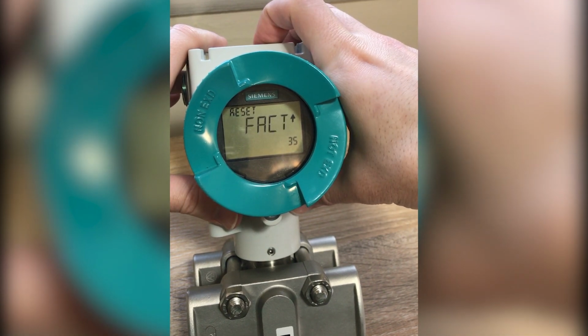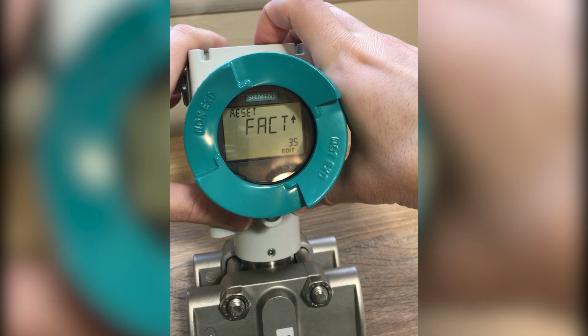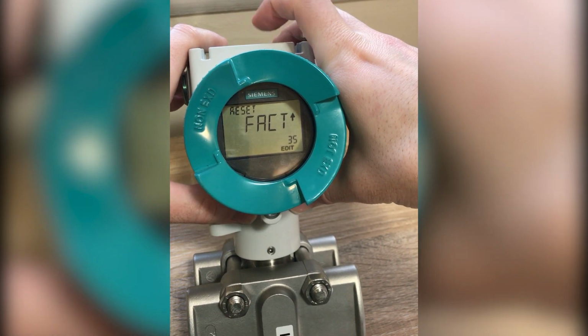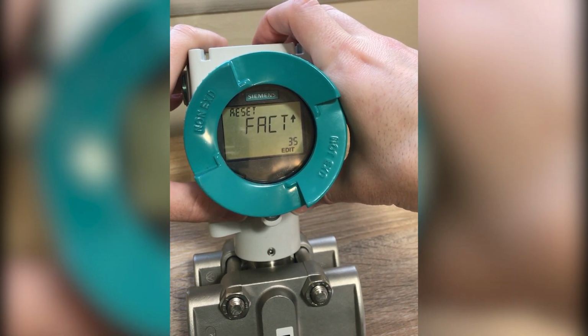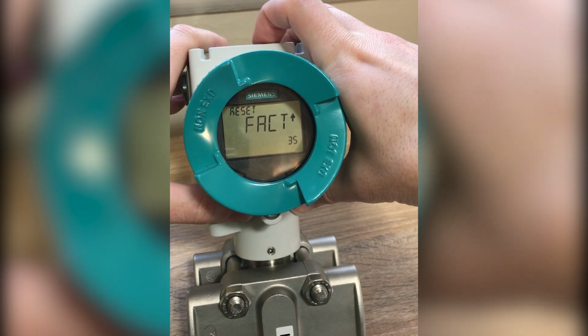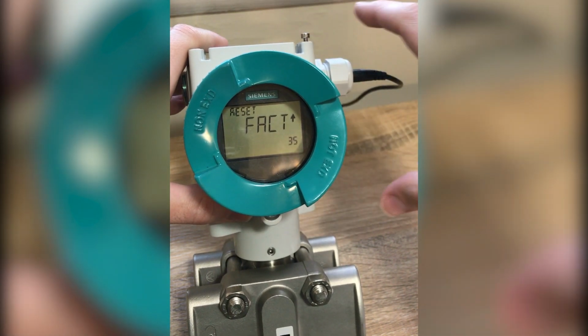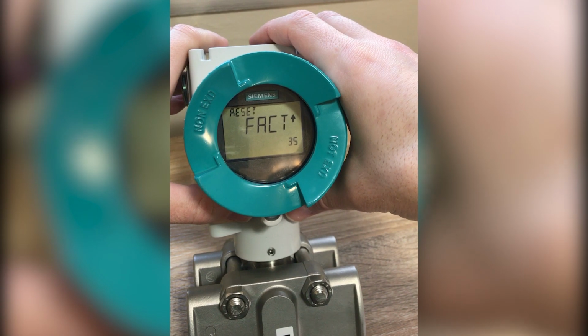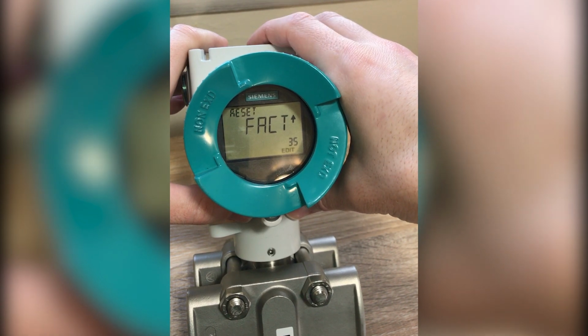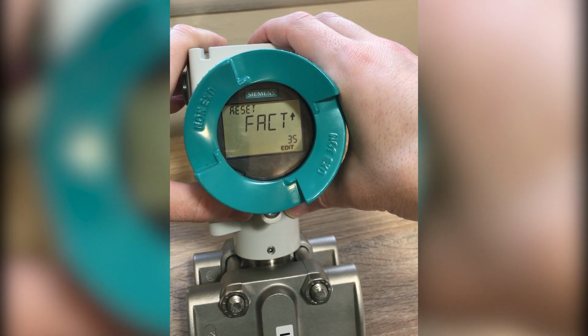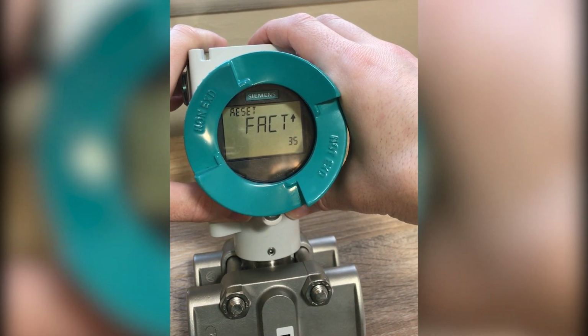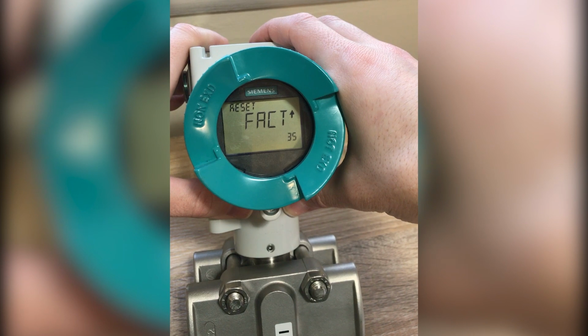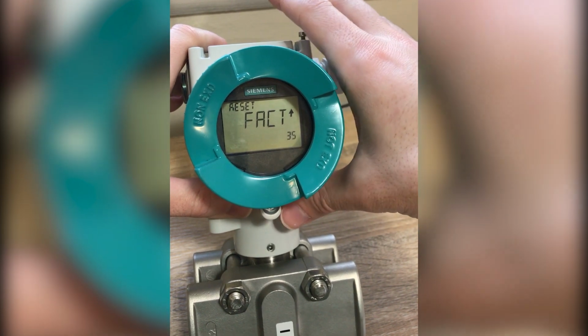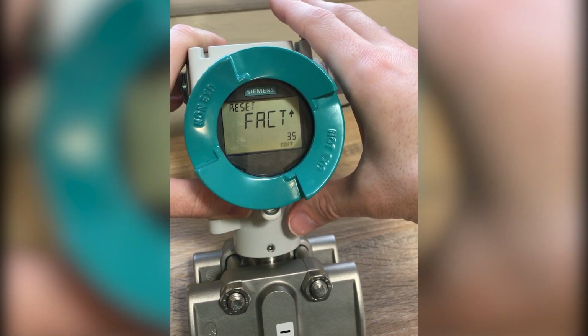The last option is FACT, for factory. This will reset the sensor, reset the digital to analog converter, as well as any other configurations. So if you perform a factory reset and you had a Y01 or some other option code in the original order, that will get reset back to factory defaults, as if it was ordered without any option codes in the model number configuration.